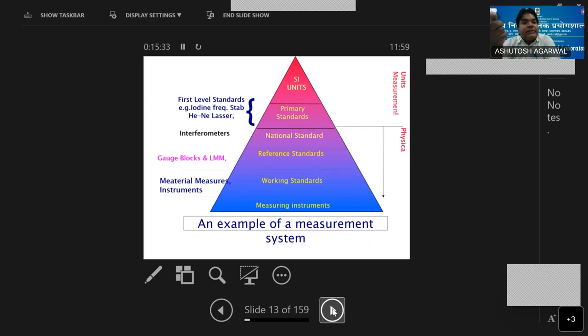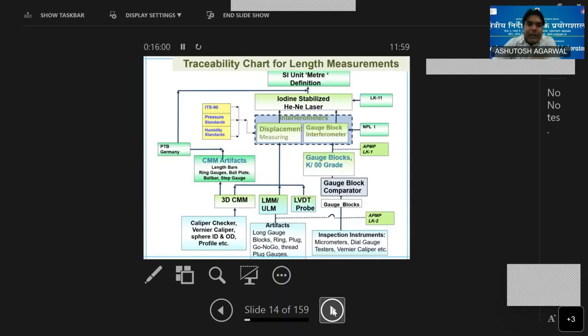So we call it secondary and reference standard. Then there are working standards like caliper checker, vernier, gauge block, slip gauge. These are the working standards. And then measuring instruments, because on site you cannot always take your gauge block comparator, so maybe that kind of probe you check. So there are working standards. So for traceability of length measurement, you can understand this very nicely now.